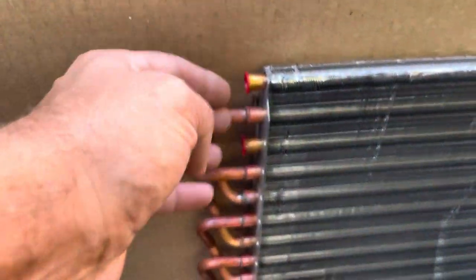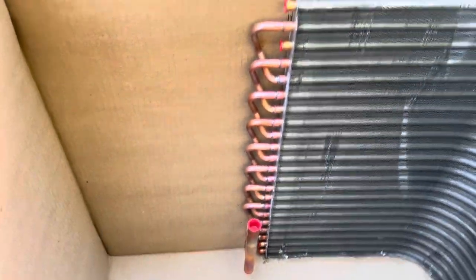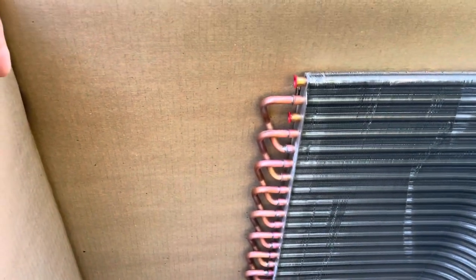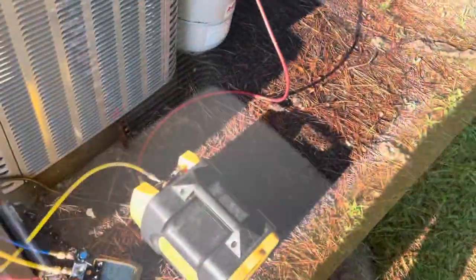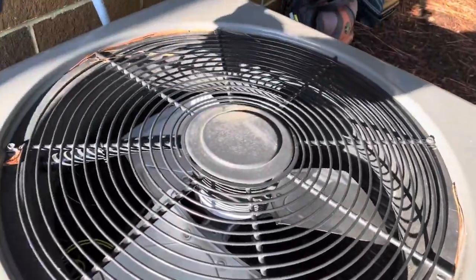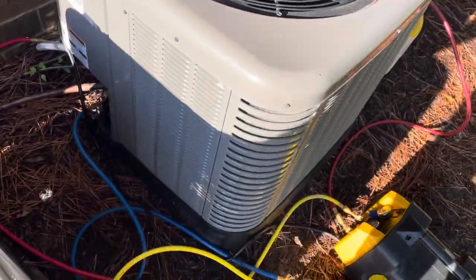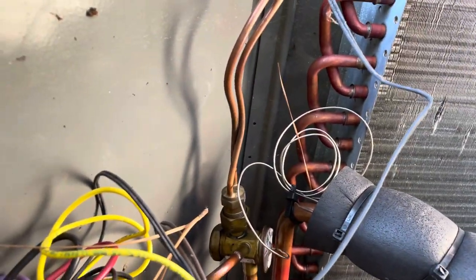Most of the time everything comes out here and you've got one distribution tube, but nope — Rheem is making us braze a whole bunch of stuff on a brand new coil. We're recovering now and we're going to start breaking this bad boy down. This is where she was leaking at, down there. You can see it real good from over here. I thought I had asked for a TXV on this one too, but I guess not.